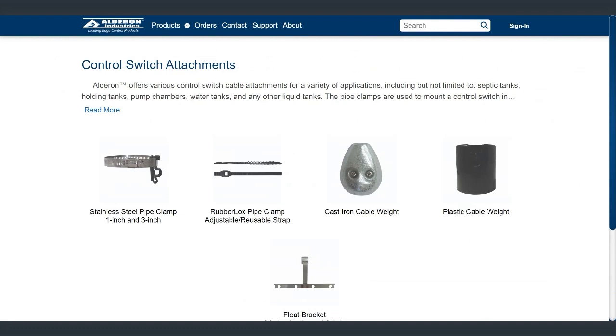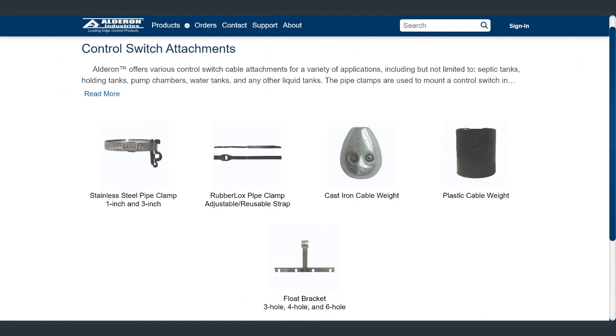Float tree bracket. If you get this, you get a couple little clips that pop in here too. You just put the clip around your cable, and then you can adjust it wherever you want, and it just sits there, and you bolt that to your riser or your concrete wall or whatever. And now your float is set. In a situation like this, you would have either plastic or cast iron weight. So you have a pivot point somewhere halfway down in the tank or the pivot.